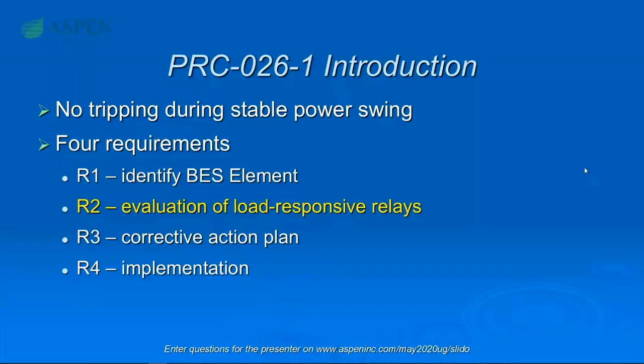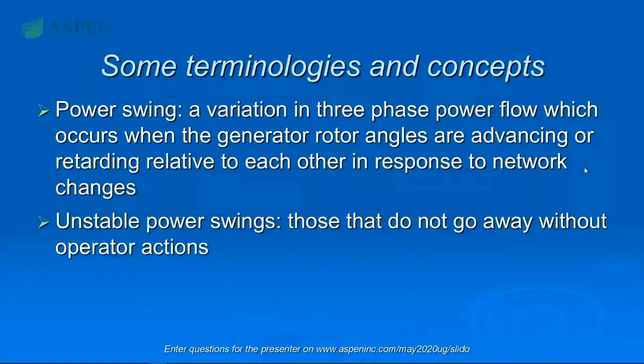This is important to keep in mind — this is, in my opinion, different from a detailed transient stability study. All you need to do is show the auditor when they come that you have met the criteria in the standard, and Aspen has a tool for you to use for that. Before going further, for those not familiar with the topic: a power swing is defined in the standard. When a power swing happens in the system, it can die down by itself or it can amplify. The second class — the unstable swing — is the one to be worried about, requiring tripping. But if the swing is stable and will die by itself, you should not trip on that.